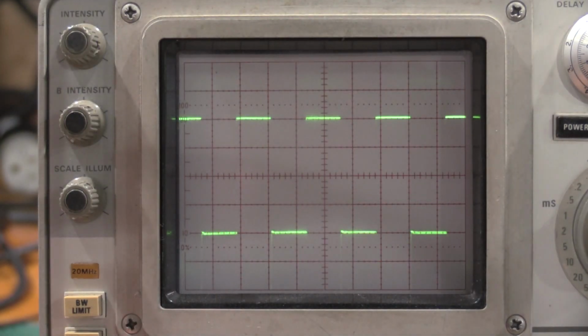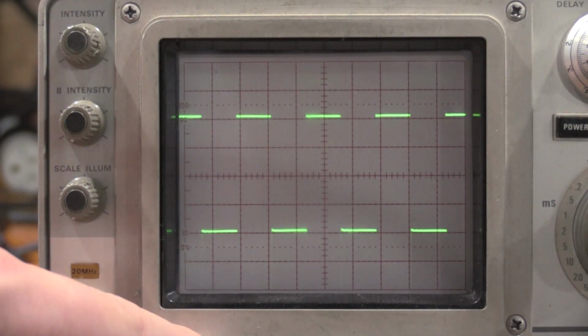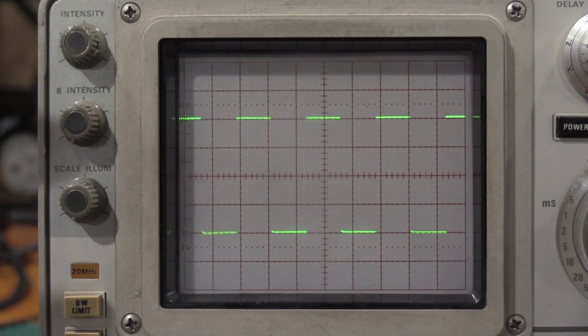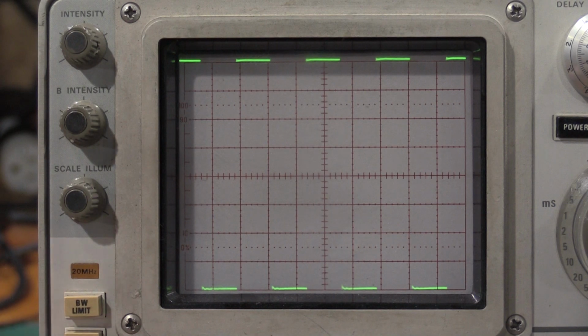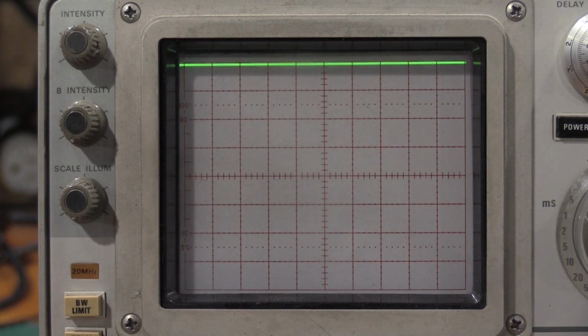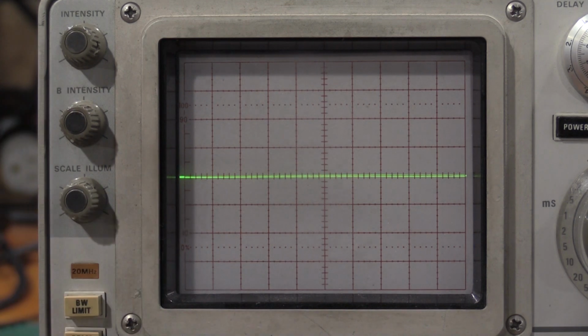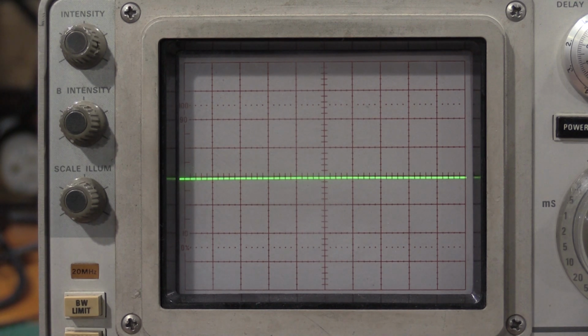I have one of my dual BNC cables hooked up to the 106. I'm just checking channel 1 and channel 2. We have 4 divisions of display, so if I hit add, we should get 8, which we do, and then if I invert, we should get no deflection, which I do, so the additive gain is adjusted correctly, and no problem there.